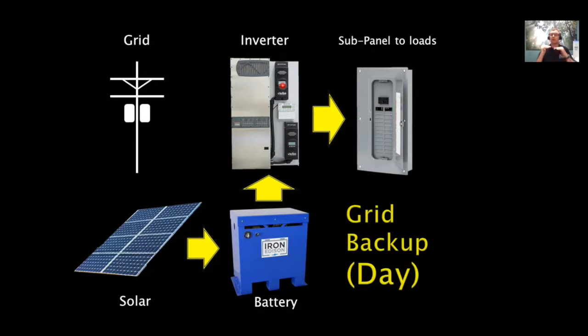Rather than taking my battery all the way down while that pump is running, I'd much rather keep my battery full all day, ask for a little help from the generator, and when that big pump goes off after filling the trough or watering the crops for an hour or so, we're able to turn off the gen or the grid automatically and go back to running off the solar system. All of these features are programmed right in, in this case, in this Outback inverter.